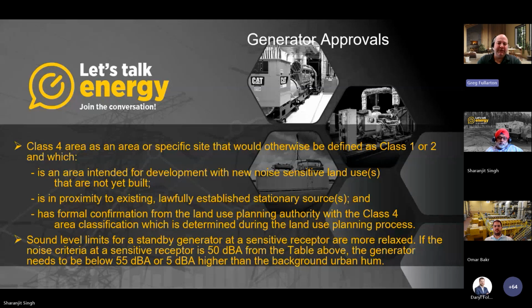A standby generator, if you were to assess the noise criteria at the sensitive receptor, you're going to assess it alone. You're not going to assess that generator with other cooling towers on the roof. You're not going to assess that generator with other equipment that makes noise at the site. It's just the individual generator that you're assessing from a noise perspective. So if the noise criteria at a sensitive receptor is 50 decibels from the table above, the generator needs to be below 55 decibels. They add a 5 decibel grace for you, or 5 decibels higher than the background urban hum, if the urban hum is in fact higher than the exclusionary sound level limits.